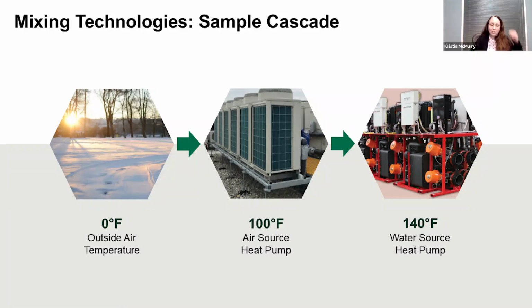You mentioned there's a portfolio of solutions, it doesn't have to be just one thing. We talked about air source heat pumps and water source heat pumps, you could use them together. So if you really want to use an air source heat pump but it can only do a 100-degree lift, you could produce 100-degree water and then have it interact with a water source heat pump that lifts it even higher, to 140 or more.